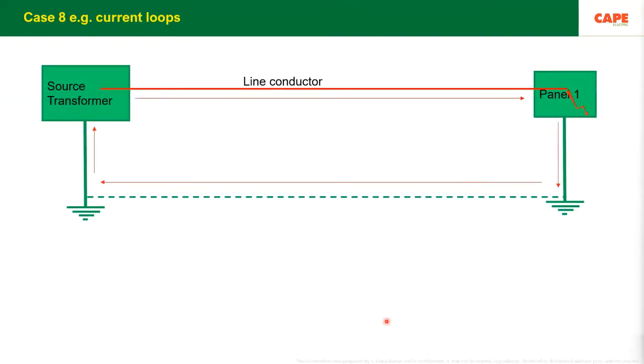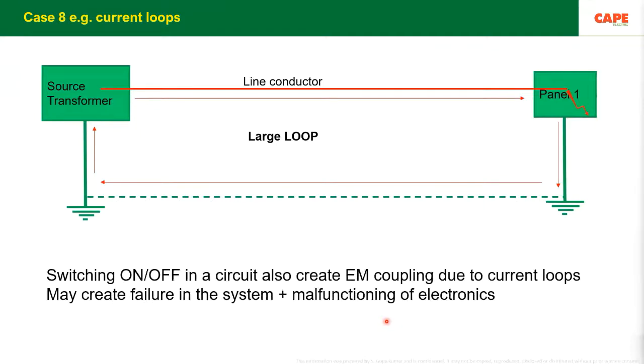Every electrical wiring shall be made in such a way that the circulating current has to take the shortest path back to the source. If we take a longer path, it may create problems such as electromagnetic interference, and it can make your electronics malfunction.